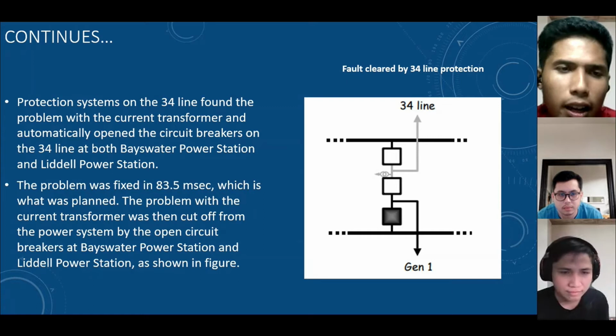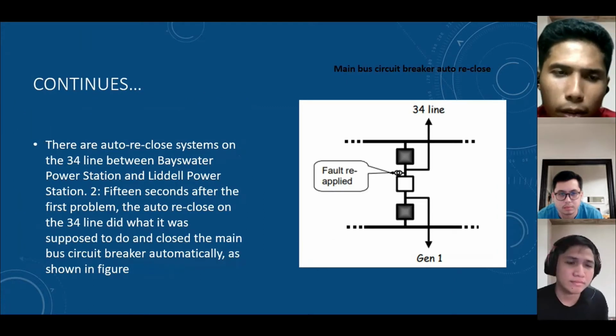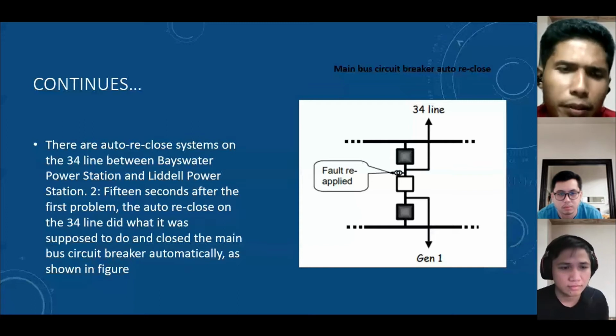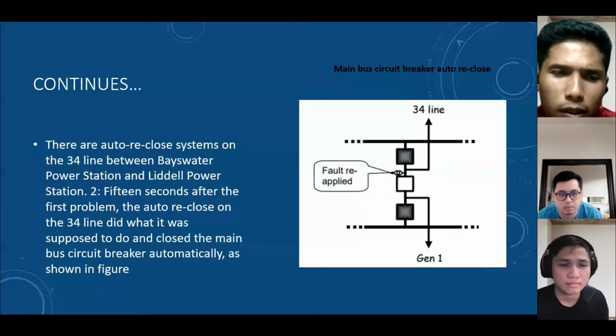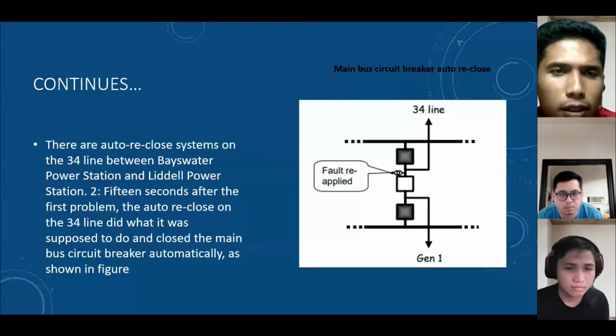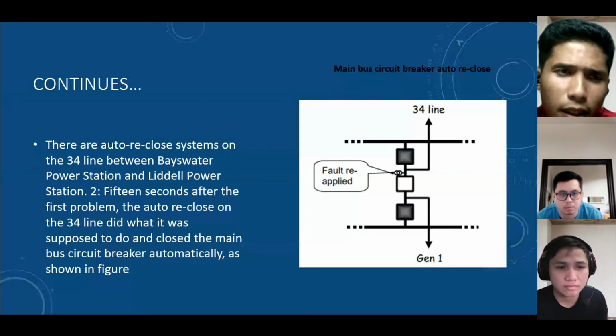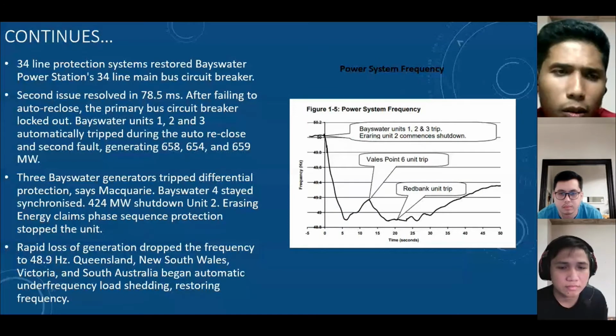Next, there is an auto reclose system on the 34 line between the Bayswater Power Station and Liddell Power Station. Fifteen seconds after the first problem, the auto reclose on the 34 line operated as it was supposed to. The 34 line protection system operated again at Bayswater Power Station. The second fault was cleared in 78.5 milliseconds. After failing to auto reclose, the primary bus circuit breaker locked out.